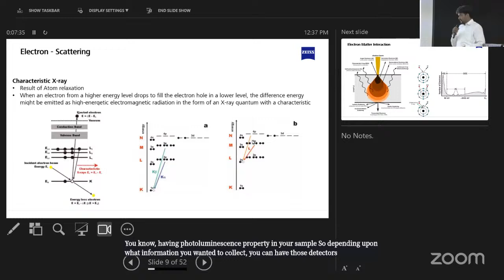You can see here, this is the incident electron beam, and this is what we call the volume of interaction within the sample. Secondary electrons, from the outermost orbit, have the surface information, which is the result of inelastic scattering. This is what happens with elastic scattering: no interaction, but they take high directional secondary electrons, or the backscattered electrons that come from the sample, and it gives you the phase or material contrast information. And during the relaxation process, one form of energy gets emitted in the form of characteristic X-rays, which is used for your chemical composition analysis.